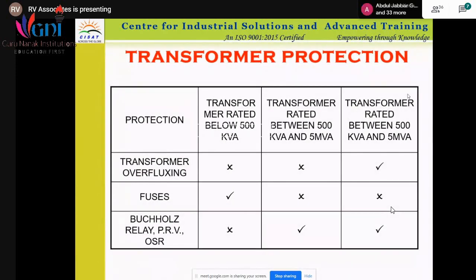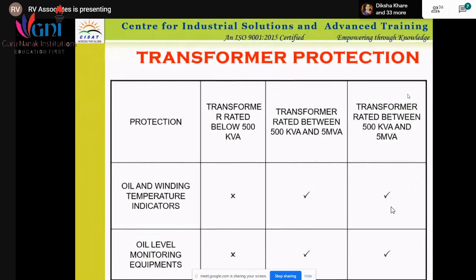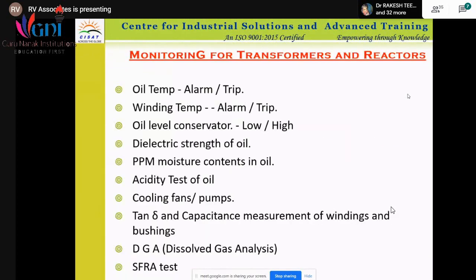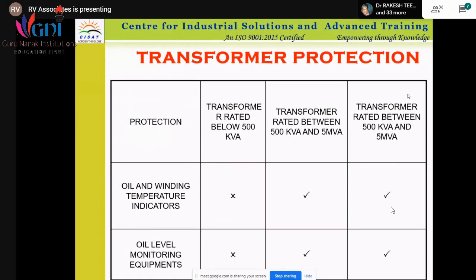Then there are various other parameters: transformer overfluxing, fuses. Then we use the Buchholz relay, PRV, and oil surge relay. These are all the protective systems, because we have to protect our transformer. Various instruments we use, like WTI, the winding temperature indicator, and the oil temperature indicator. Then there are relief valves, which relieve the gases produced in the tank of the transformer. So these are all the monitoring and protective equipment.